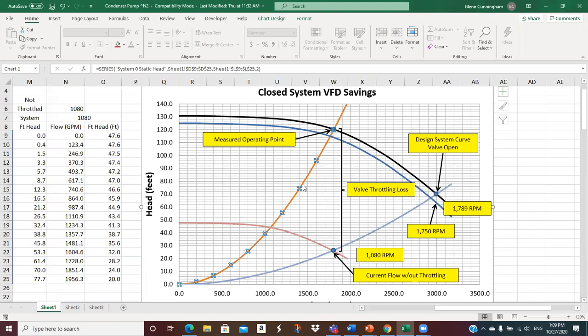Okay, now, you know, how am I going to save them energy? Well, they're dropping a huge, look at the feet of head dropped across the valve. Those valves, I think this thing actually had two valves on them, and they were both pinched. Because they couldn't pinch it with one valve, they got cavitation and they tore the valve up. So they said, well, we'll pinch this one a bunch and we'll pinch this one a bunch to get the flow down to where we need it, because this pump is grossly oversized.